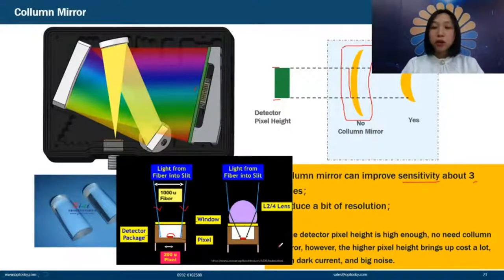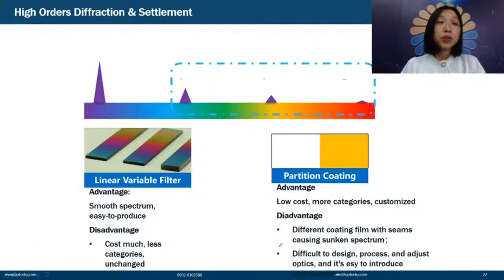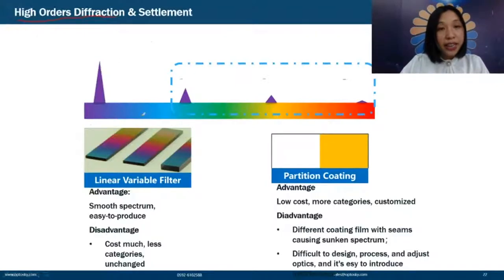After the cylindrical mirror, we introduce higher-order diffraction and how to eliminate it. Gratings generate not only the useful first-order peak (e.g., at 200 nm) but also second-, third-, and fourth-order peaks appearing at 400, 600, and 800 nm. These are harmful peaks that distort measurement results. We must eliminate them while keeping only the useful first-order peaks.